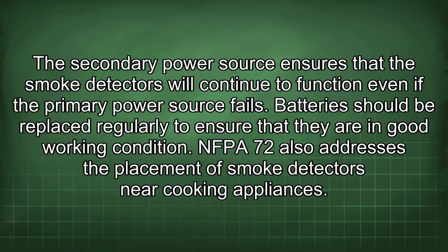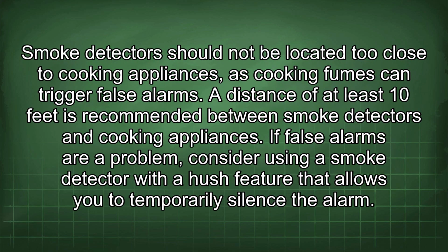NFPA 72 also addresses the placement of smoke detectors near cooking appliances. Smoke detectors should not be located too close to cooking appliances, as cooking fumes can trigger false alarms. A distance of at least 10 feet is recommended between smoke detectors and cooking appliances. If false alarms are a problem, consider using a smoke detector with a hush feature that allows you to temporarily silence the alarm.